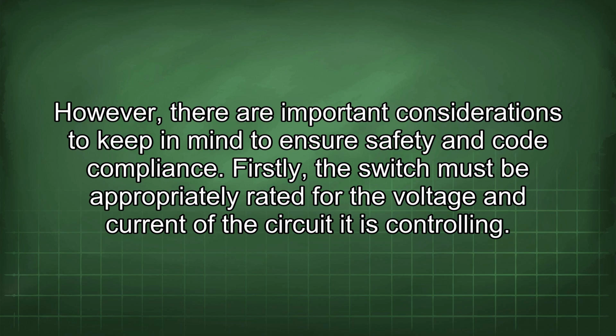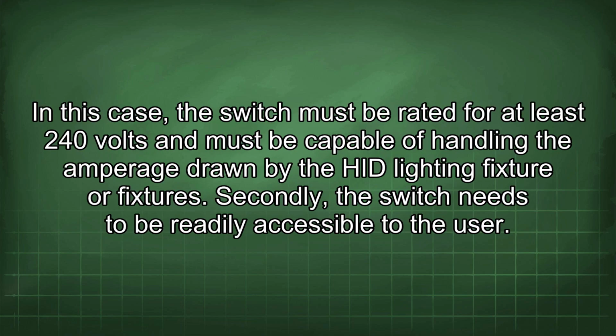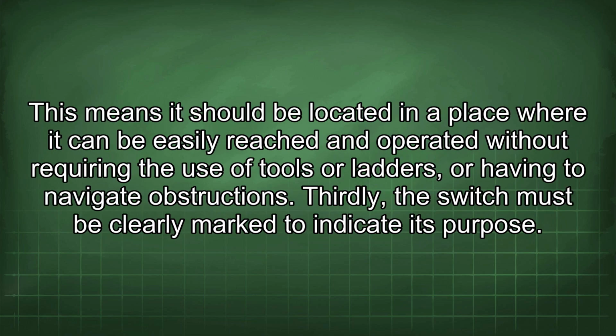Firstly, the switch must be appropriately rated for the voltage and current of the circuit it is controlling. In this case, the switch must be rated for at least 240 volts and must be capable of handling the amperage drawn by the HID lighting fixture or fixtures. Secondly, the switch needs to be readily accessible to the user. This means it should be located in a place where it can be easily reached and operated without requiring the use of tools or ladders, or having to navigate obstructions.